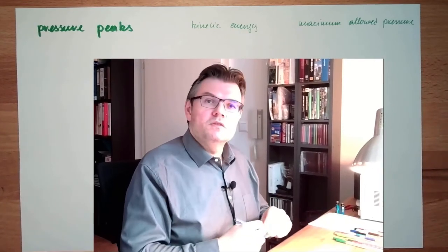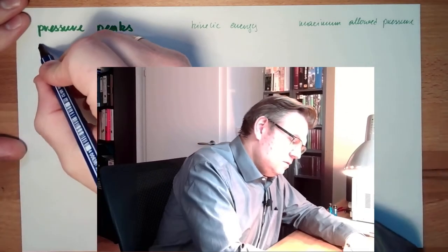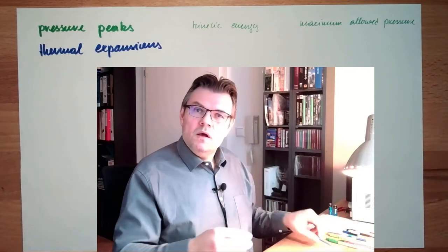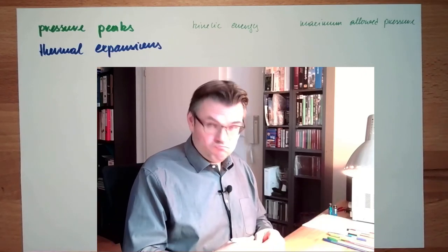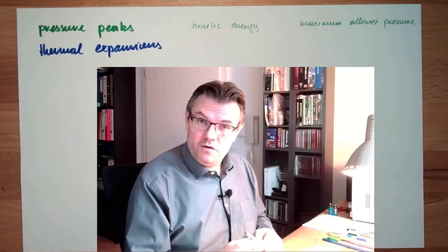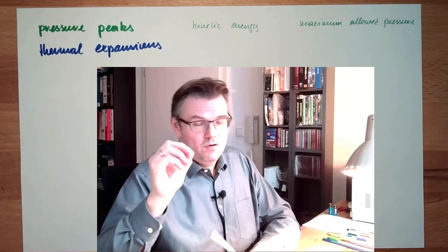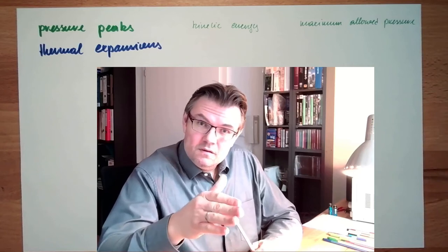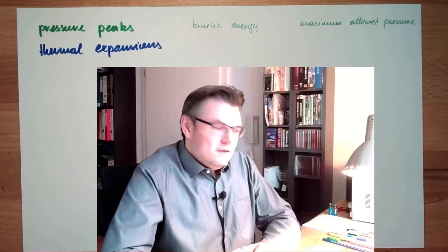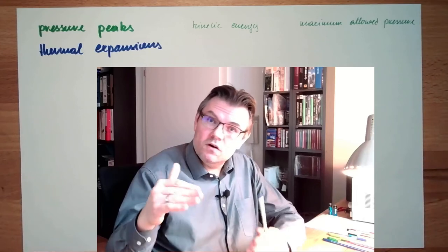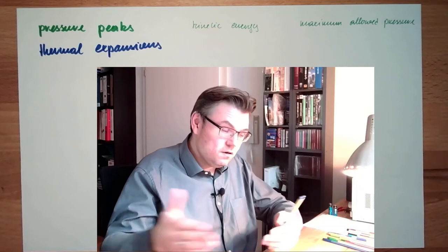Then there would be the possibility of thermal expansion. If the liquid is getting warm, the volume of the liquid is getting more, and since it's hardly compressible, this additional volume has to go somewhere. In every heating system, or in a lot of heating systems, if you are warming up water, then you need somewhere such a thermal expansion storage. The excessive volume, because of the additional temperature, needs to go somewhere.